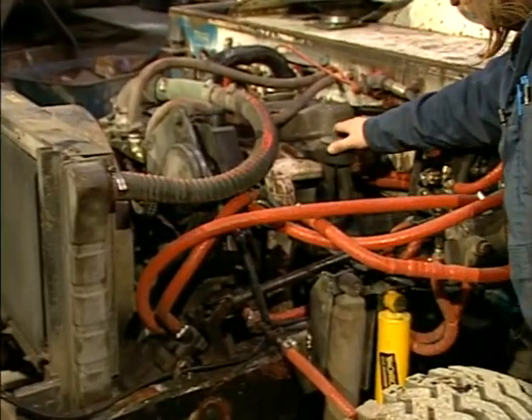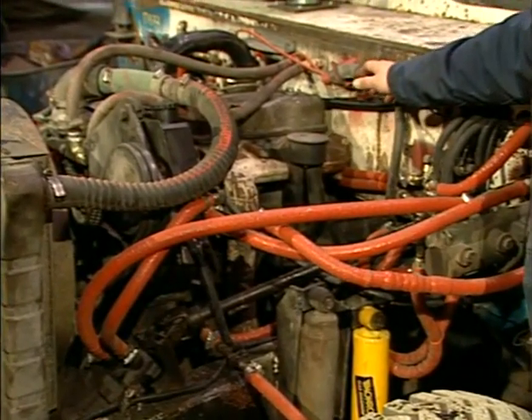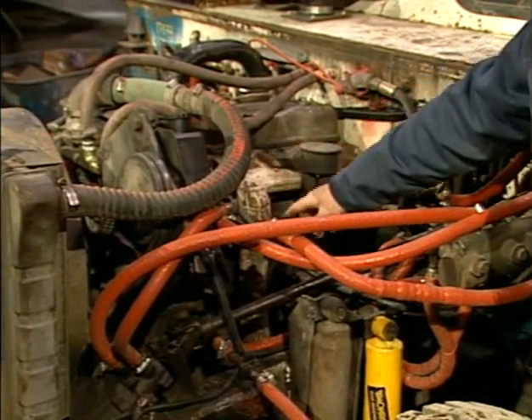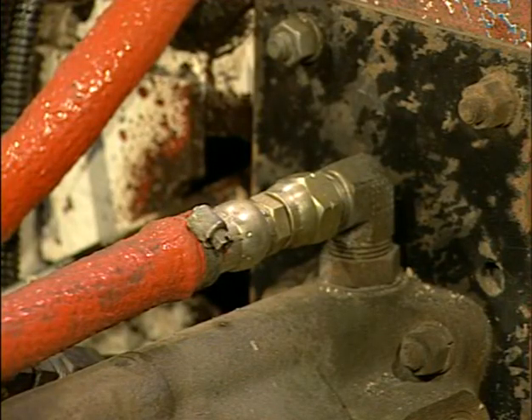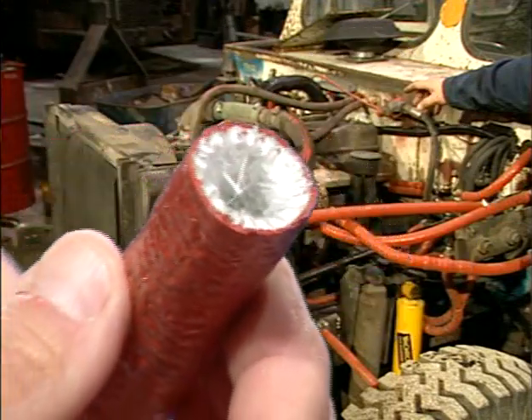The regulation requires a means to prevent spray from ruptured hydraulic and lubricating oil lines from being ignited by contact with engine exhaust system component surfaces, such as the exhaust manifold and exhaust pipe. The hydraulic lines have been covered with a flexible rubber conduit, but this conduit needs to be extended to cover the fittings to provide protection if the fittings leak. Additional protection such as a ceramic coating or jacket on the exhaust manifold or exhaust pipe, or flame-resistant sleeves on the hydraulic hoses, should also be used.